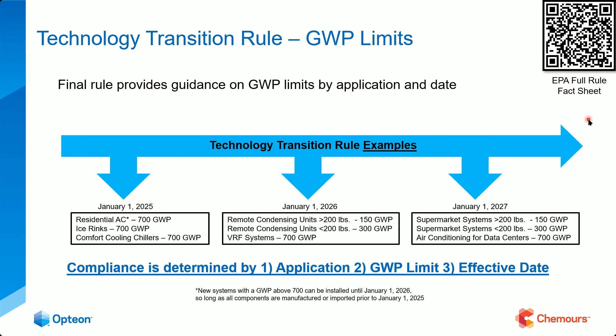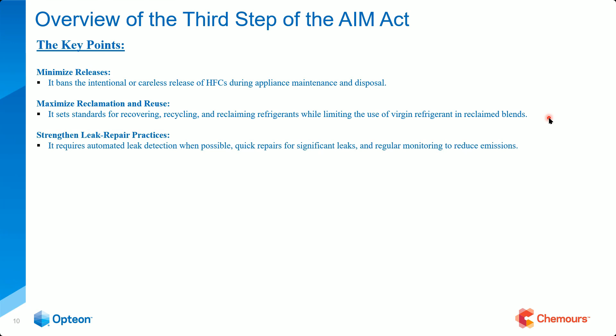There is a QR code if you want to scan this up here for the EPA full rule fact sheet. Now, the third step, the key points are minimize releases. It bans the intentional or careless release of HFCs during appliance maintenance and disposal. It maximizes reclamation and reuse. It sets standards for recovering, recycling, and reclaiming refrigerants while limiting the use of virgin refrigerant in reclaimed blends. It strengthens leak repair practices. What that means is it requires automated leak detection when possible, quick repairs for significant leaks, and regular monitoring to reduce emissions.